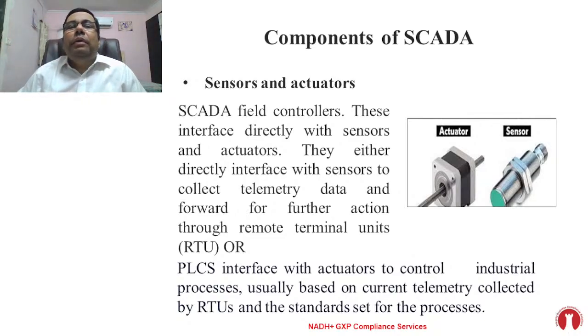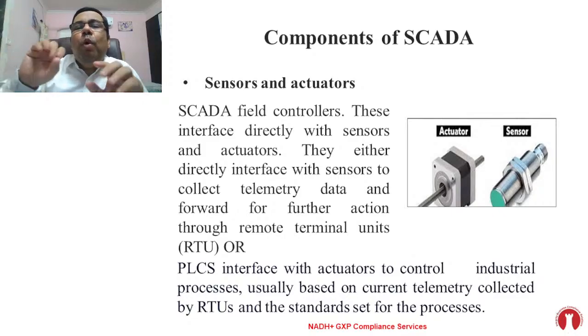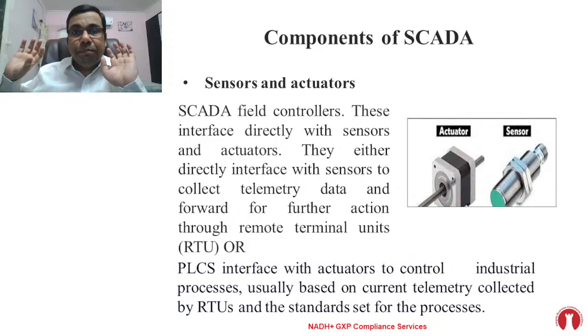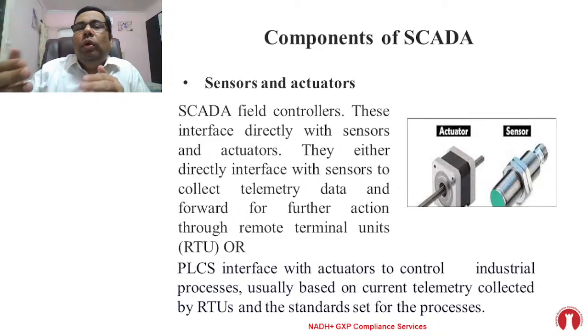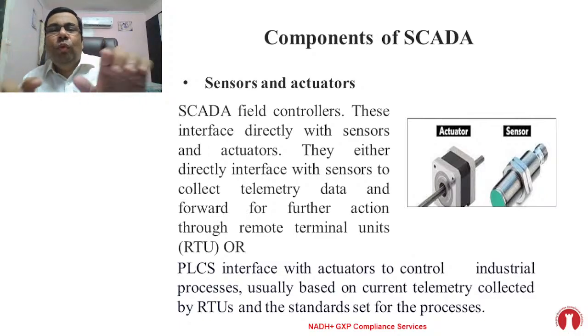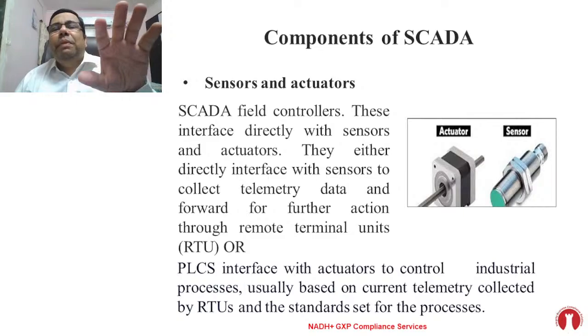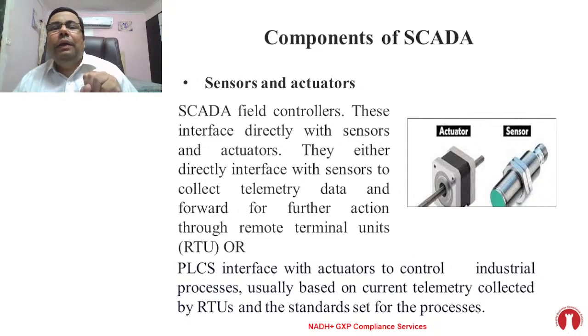SCADA field controllers interface directly with sensors and actuators. They either directly interface with sensors to collect telemetry data, meaning collect real-time data, and forward it for further action through remote terminal units, RTU. PLCs interface with actuators to control industrial processes, usually based on current telemetry collected by RTU and standards set for the process. These words are confusing, but simply, sensors and actuators are part of SCADA - the first component. Sensor collects data, actuator gives the output, such as working valves and similar operations.